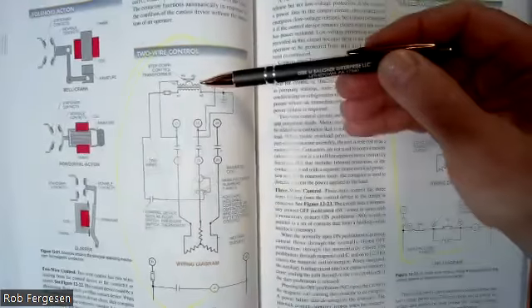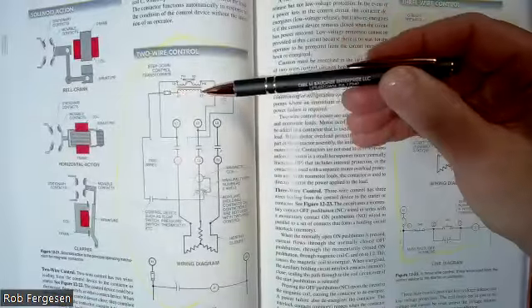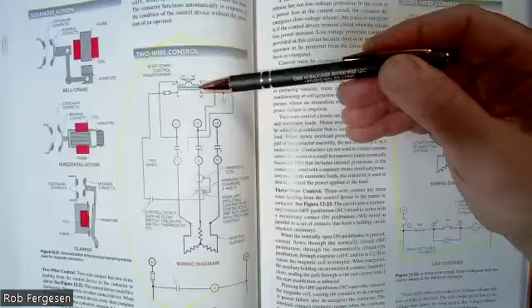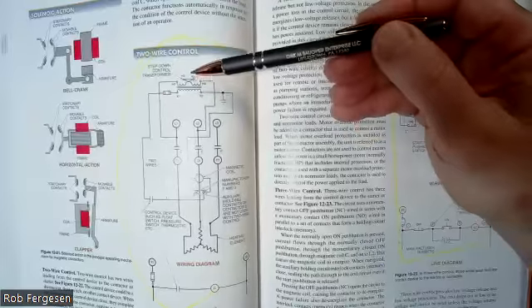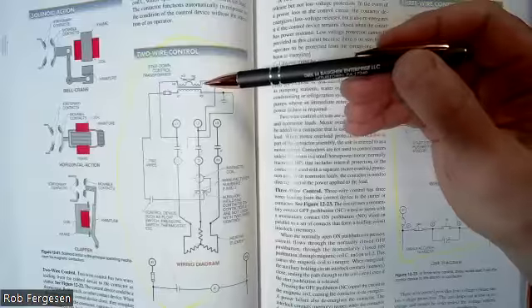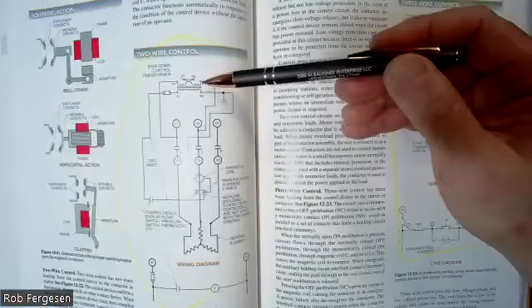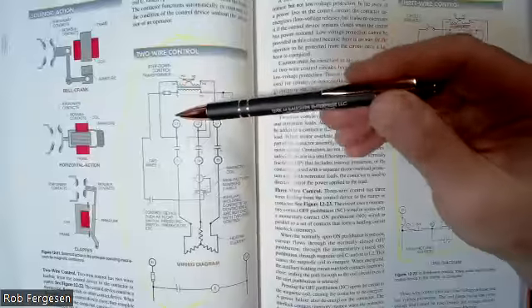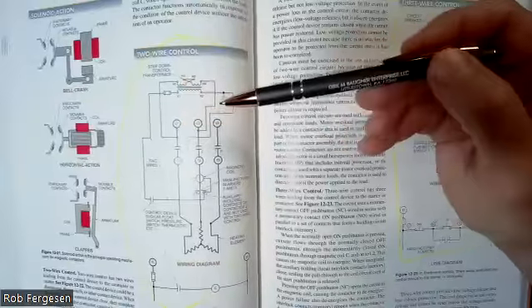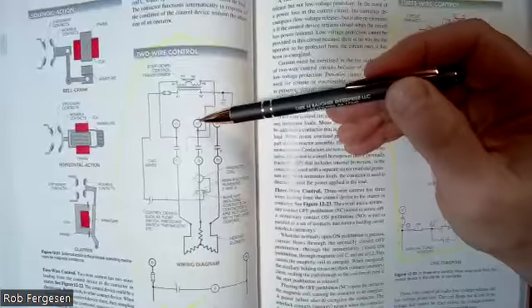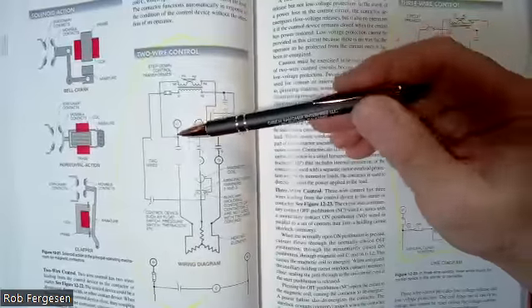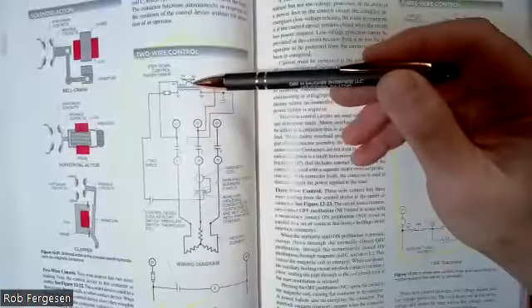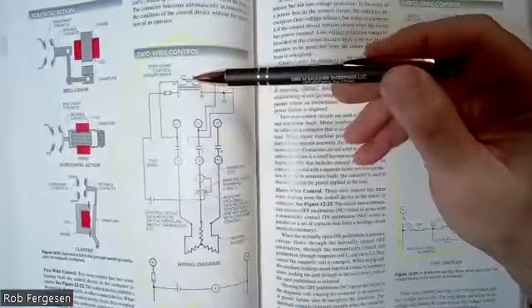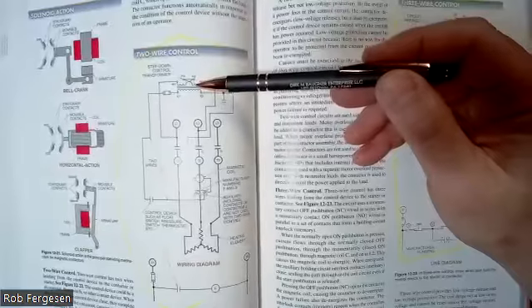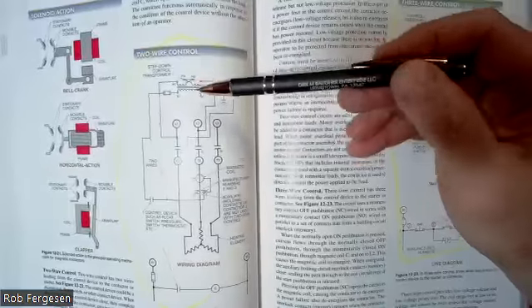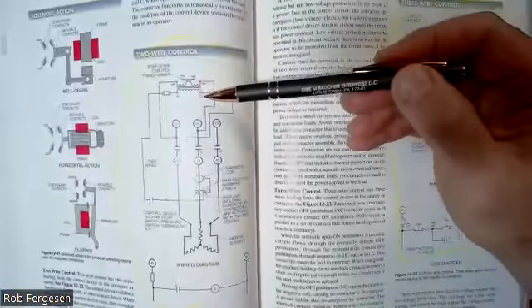At the top of the high power, I've got a control transformer, step down control transformer, nicely labeled, right? You can see I've tied together H3 and H2, and I've hooked up H1 and H4 to the first legs, leg 1 and leg 2 of my primary three-phase power. I'm just using those first two legs to control my control transformer because my control transformer is just giving me my single phase control power, probably 120 volts. They don't specify it here, but it's probably 120.